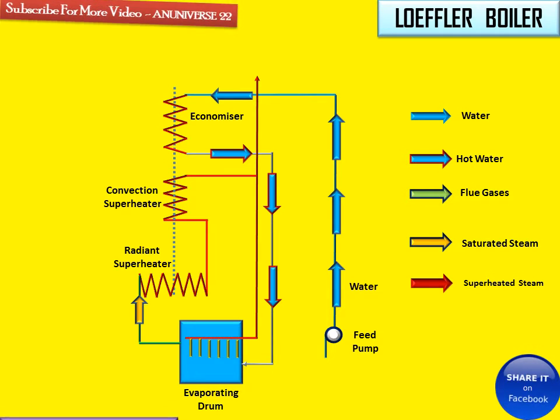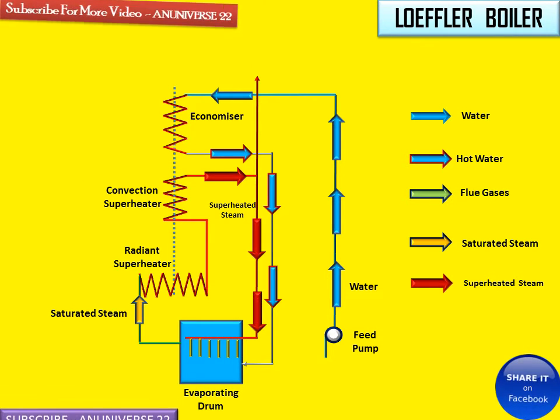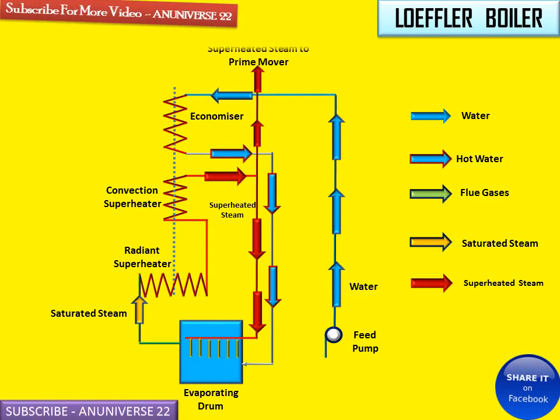From the evaporating drum, saturated steam is supplied to the radiant superheater, and from the radiant superheater it is supplied to the convection superheater, where the temperature of the steam is increased and it becomes superheated steam. One third of this superheated steam passes through to the prime mover, and the remaining two thirds is supplied to the evaporating drum in order to evaporate the feed water.